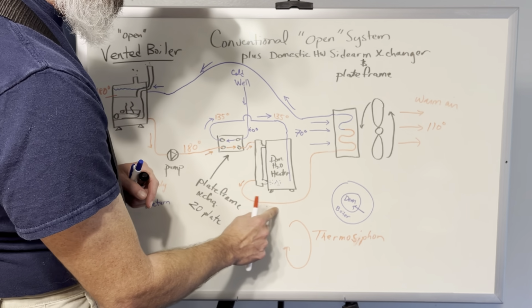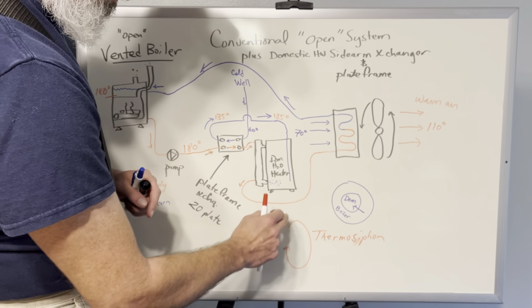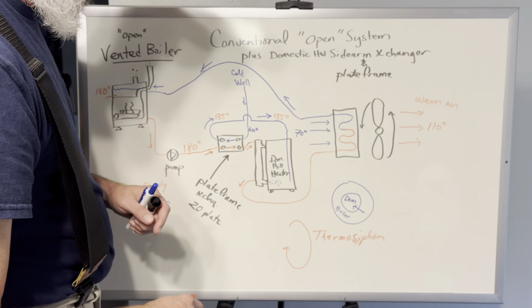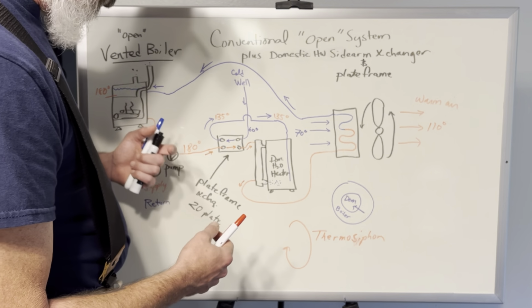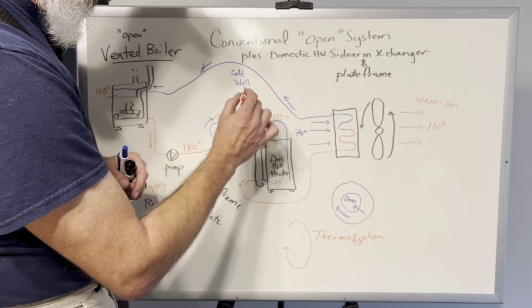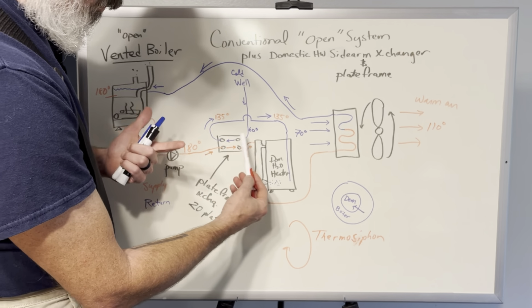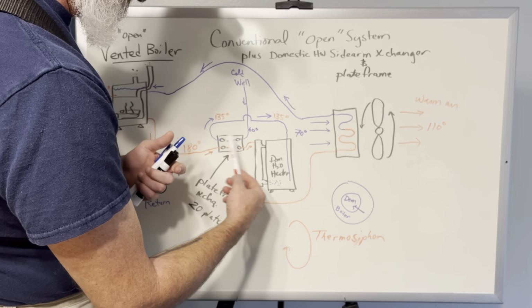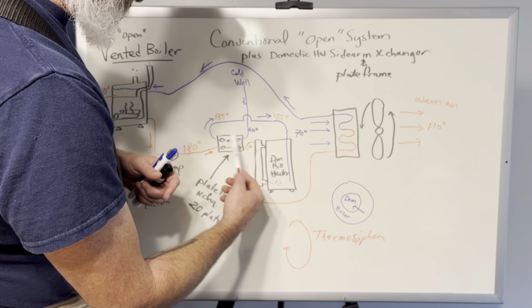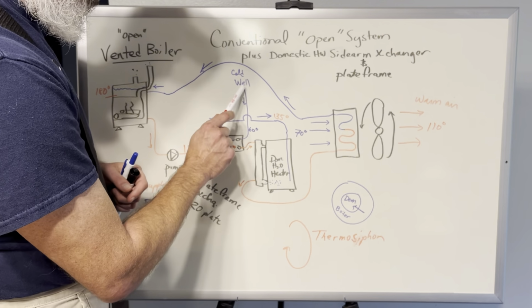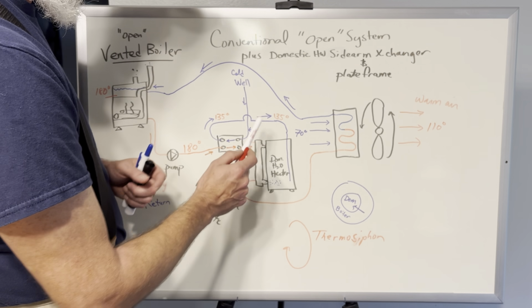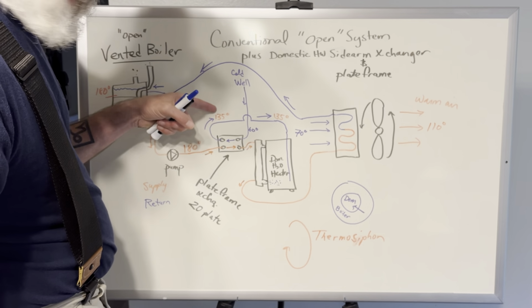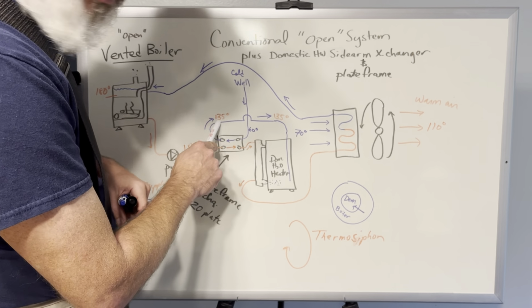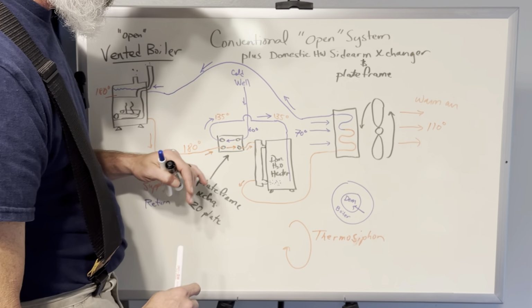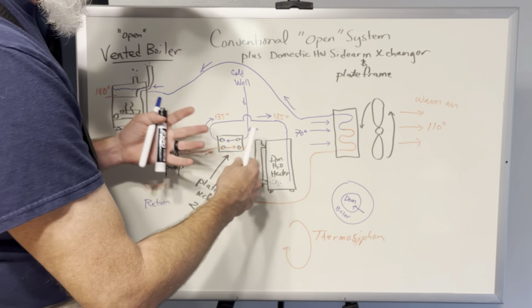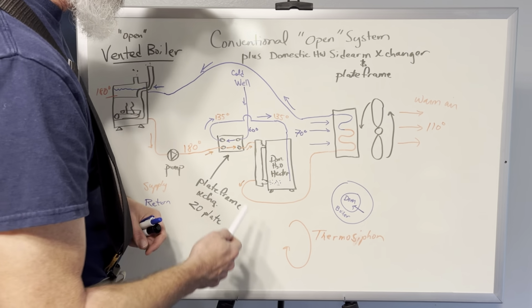Now let's say that mama bear and your daughters are taking a shower. Well, flow through here will be fairly substantial. Maybe 3 or 4 people are taking showers. This may be 5-6 gallons a minute, but we'll have some flow. And so that cold water from your well goes into that heat exchanger. Let's say it's going in at 60, and I'm saying 135 degrees. That number is very arbitrary. It depends on how big the plate frame heat exchanger is and how much water flow is going through there. But it'll be coming out ideally hot if you've sized everything correctly.